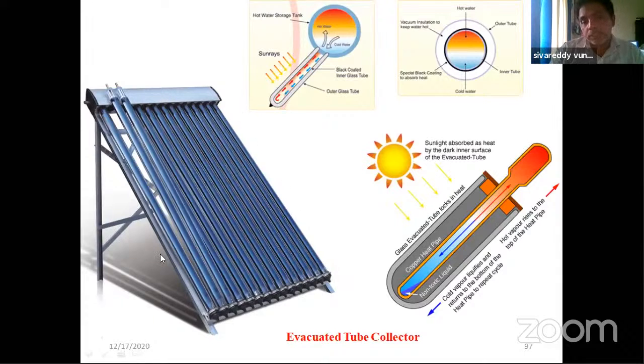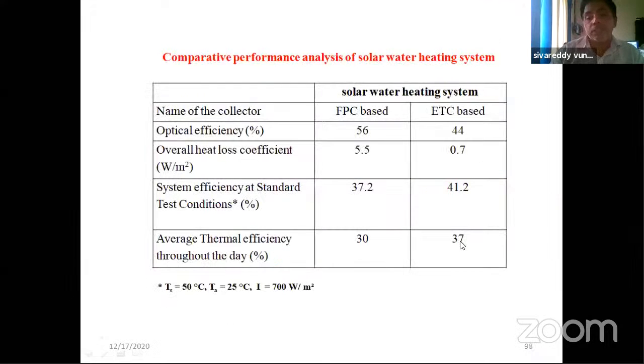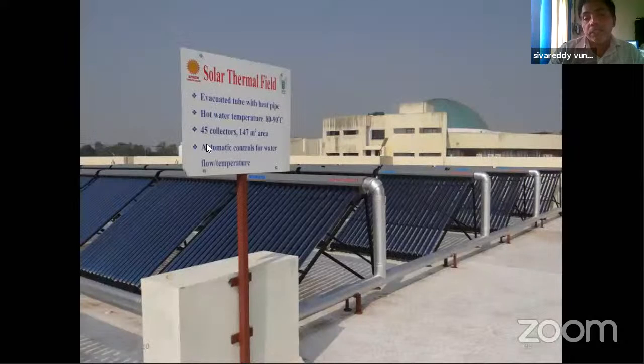Suppose one collector system fails, our process is not affected. Maybe the temperature rise will reduce, but leakage will not take place. Why? Because the water is flowing in the manifold, not in the tubes. That is one advantage. And effective transfer of heat from the end point to the manifold is easy by the heat pipe. Even with a lower temperature difference, we can generate effective heat transfer. We connected 45 collectors in 5 rows, with a 147 square meter area.